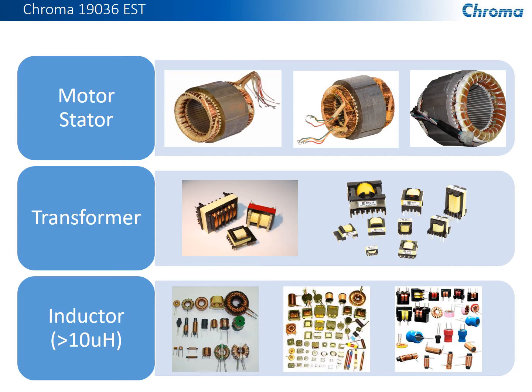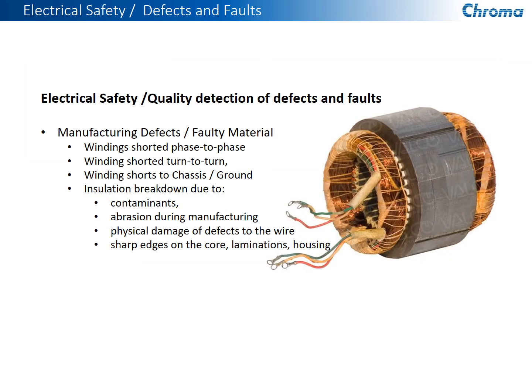If you've ever seen how these devices are actually manufactured, either by hand or using automated devices, the windings can take a real beating during the process. So the wire used in each of the windings uses just a varnished enamel type of insulation. In between the layers, there may be other types of insulation. So all of these things, if damaged, can produce some major problems for any one of these devices. So electrical safety detection of defects and faults is mandatory. It's even defined in many different standards.